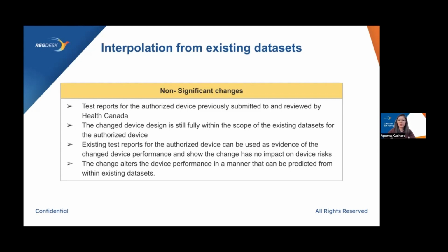Another example would be, let's say, a changed device design is still fully within the scope of the existing data sets and there are no deviations. And one more example: let's say the existing test reports for an authorized device can be used as evidence of the changed device's performance and show the change has no impact on the device risks. So you can utilize the existing test reports to show that there is no significant impact from the device changes you will be making.